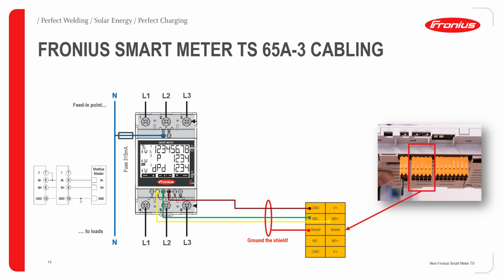And whenever it comes to data communication cabling, please remember there are 3 points which can make sure your Modbus is working fine. First, use a shielded cable and ground the shield on one side. There is an option especially for the shield in the Gen 24 series in the pilot, but in the Snap Inverter series you can use the ground to connect this. And then the other thing is to set a terminal resistor for the Modbus. Whenever you have more than 2 devices, for example the inverter Gen 24, and then the smart meter and then the battery, so you have 3 devices, the end devices always have to be terminated with this 120 ohm resistance.